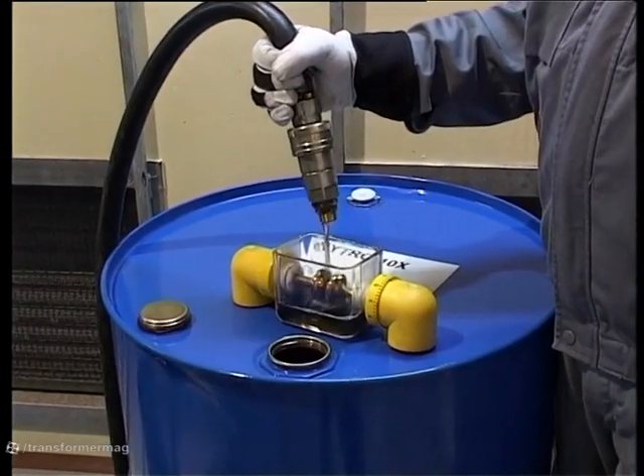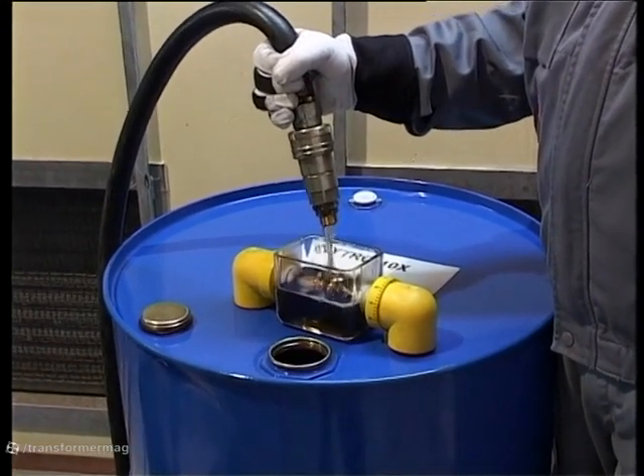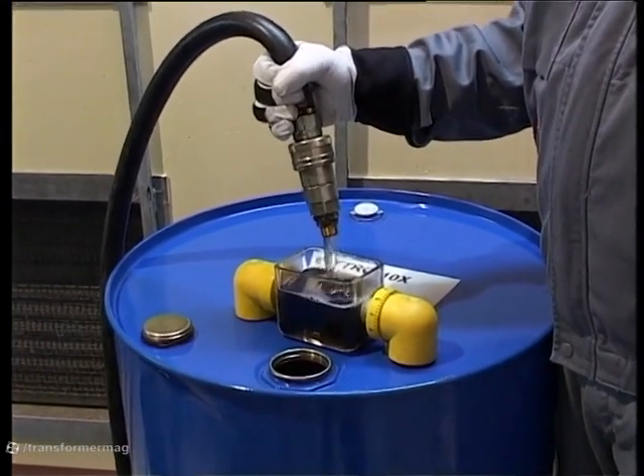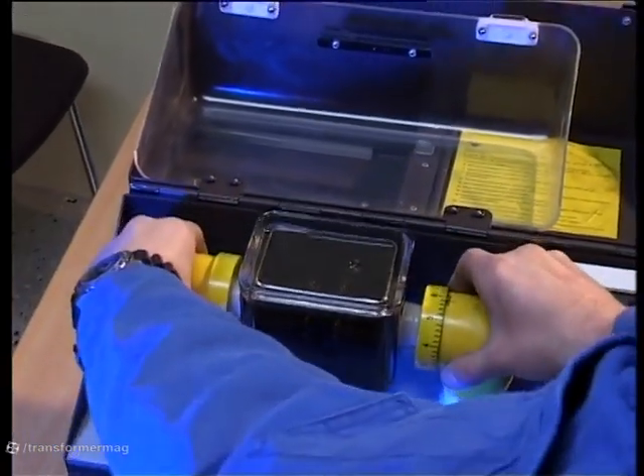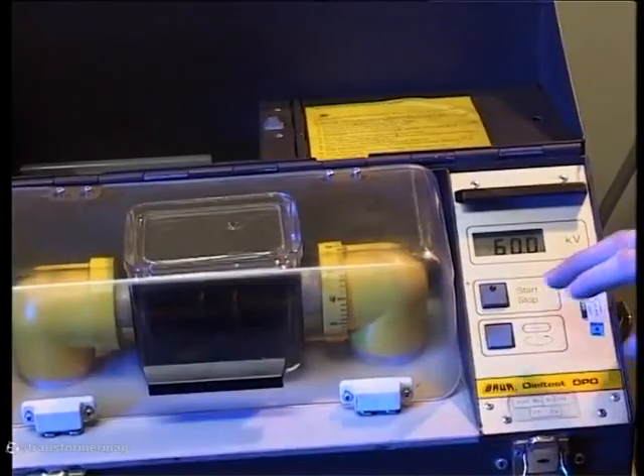The oil must be filtered. The dielectric strength after filtering must be at least 40 kilovolts with a 2.5 millimeter gap as specified in IEC 156. Here you can see a sample being taken.